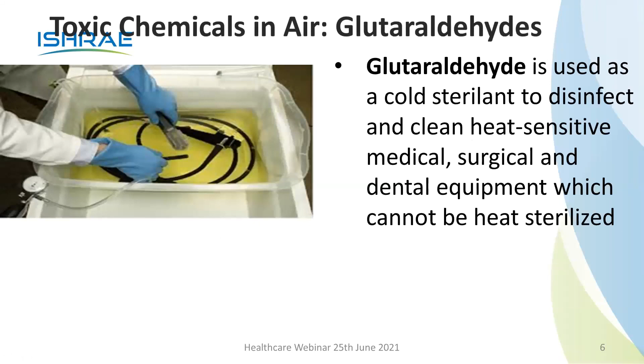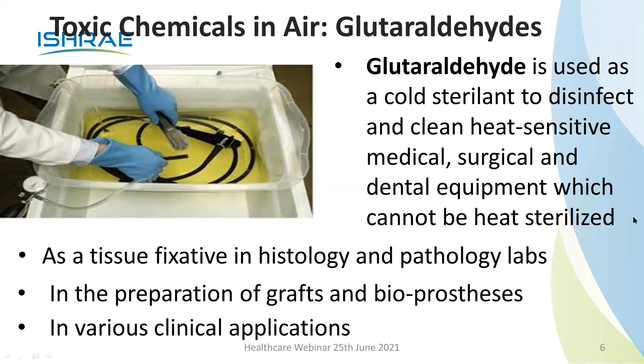Glutaraldehyde is used as a cold sterilant to disinfect and clean heat-sensitive medical, surgical, and dental equipment which cannot be heat sterilized. You know, when you cannot put it to a sterilizer, which is the safest way, there are some PVC tubes and other sorts of things that you can't put in a sterilizer. You have to use these chemicals to do the cold sterilization. So they give out some fumes. It is also used as a tissue fixative in histology and pathological labs, in the preparation of grafts and bioprosthesis, and in various clinical applications.